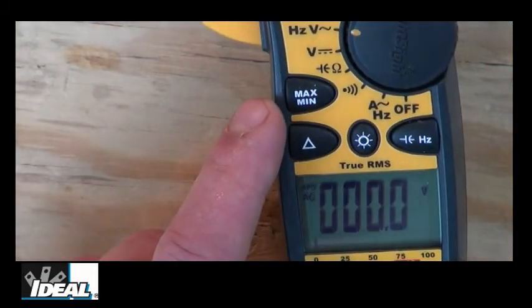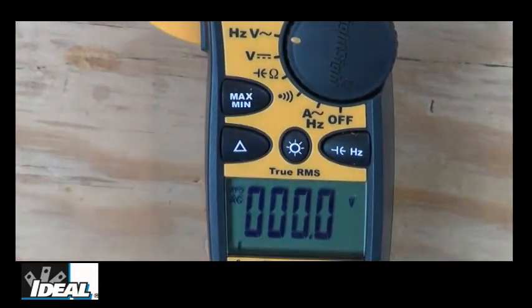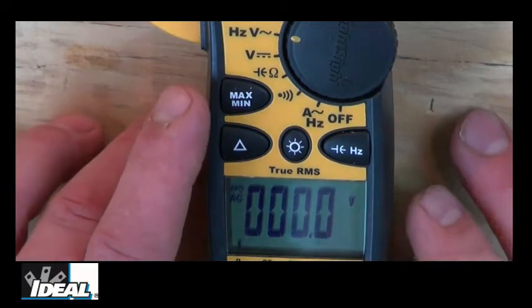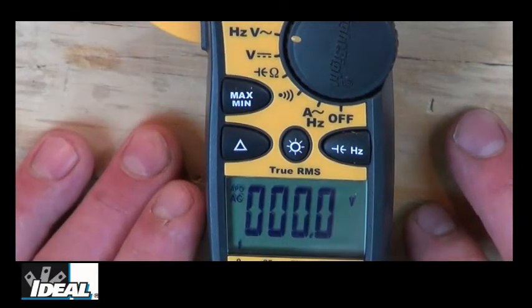You see the tester also has a min and max button on it, which is a really nice feature. And it will record the minimum or the maximum over a period of time of what it might have been reading. And you can do it for longer periods of time because the tester has an auto power off feature and automatically powers itself off in 30 minutes. But you could disable that and for a longer period of time, you can record those minimums and maximums, which is another nice feature you don't find on a lot of clamp meters.